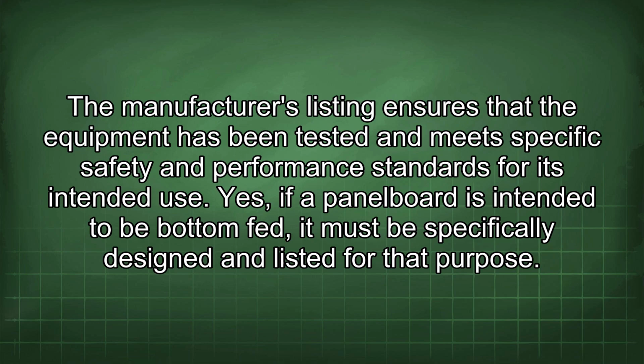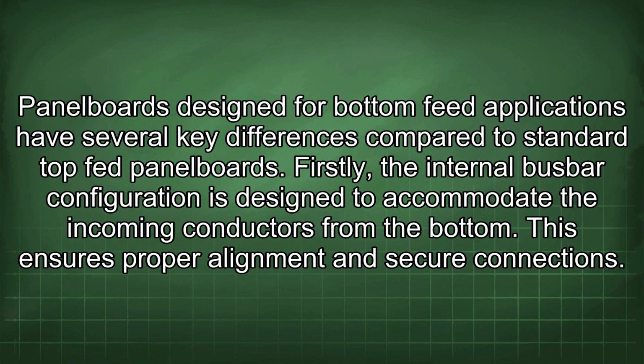its intended use. Yes, if a panel board is intended to be bottom fed, it must be specifically designed and listed for that purpose. Panel boards designed for bottom feed applications have several key differences compared to standard top fed panel boards. Firstly, the internal busbar configuration is designed to accommodate the incoming conductors from the bottom. This ensures proper alignment and secure connections.